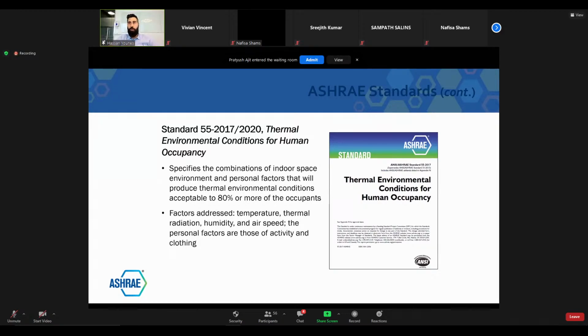For example, there's an analytical method and a graphical method. With the graphical method, above 12 grams per kilogram, you can't use it; you need the analytical method instead. Most designers use the graphical method and normally choose 24 to 25 degrees at 50% relative humidity.